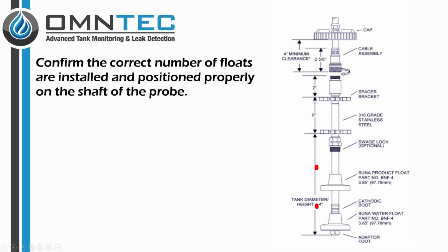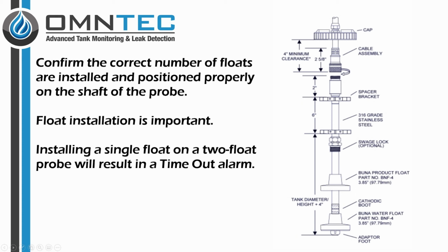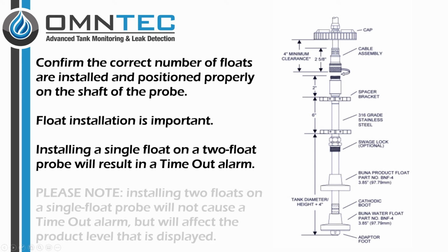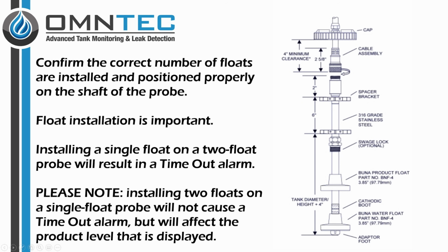Confirm the correct number of floats are installed and positioned properly on the shaft of the probe. Float installation is important. Installing a single float on a 2-float probe will result in a timeout alarm. Please note, installing 2 floats on a single float probe will not cause a timeout alarm, but will affect the product level that is displayed.